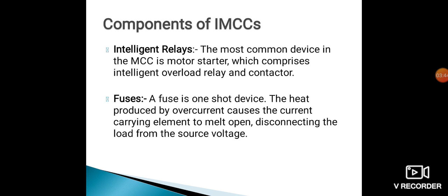The intelligent relay consists of a built-in communication facility, input terminals for monitor connection, output terminal points, status indicators, which are normally LEDs, protective functions covered, programmable parameters for the protective functions, current monitoring and diagnostics. These are the components associated with the intelligent relays.